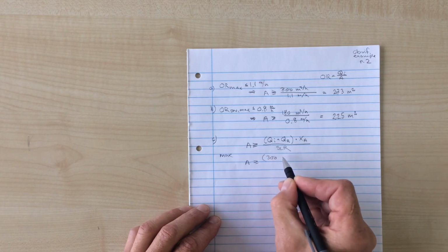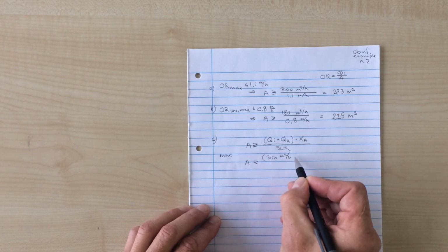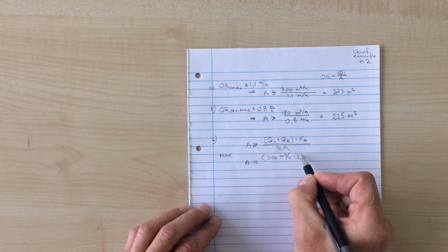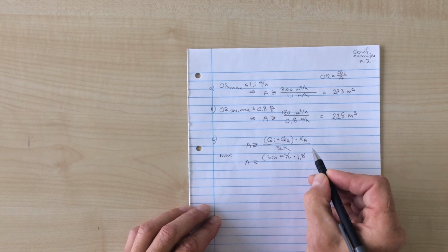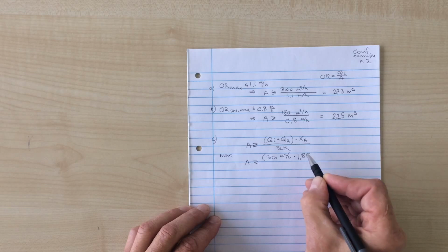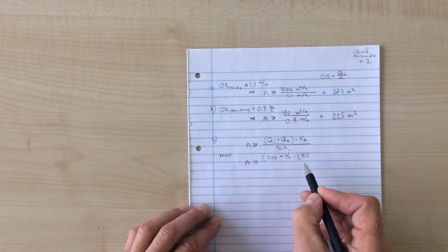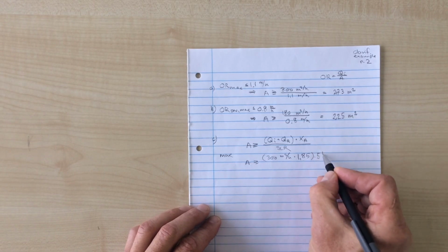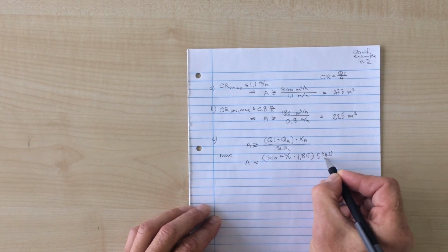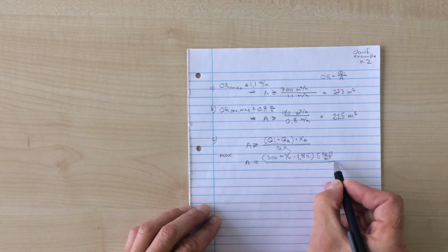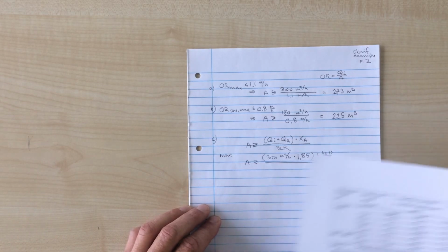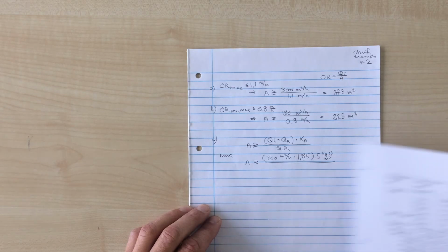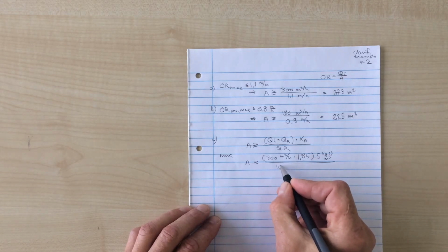In this case, for the maximum situation, I will get an area where I have 300 cubic meter per hour times 1.85, because my return sludge flow would be 85% of the inlet flow, and I have 5 kilogram suspended solids per cubic meter, or up to that, and my acceptable solids loading rate was 10 kilogram per square meter per hour.